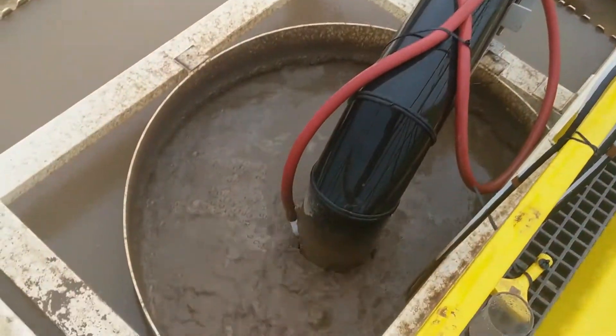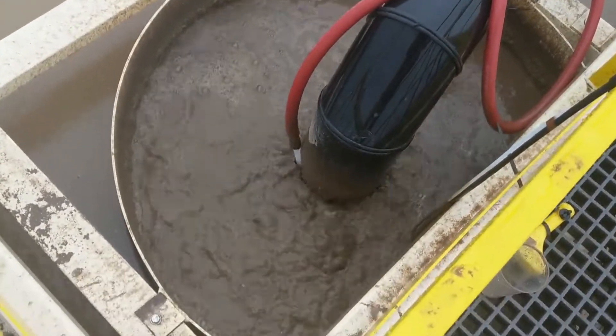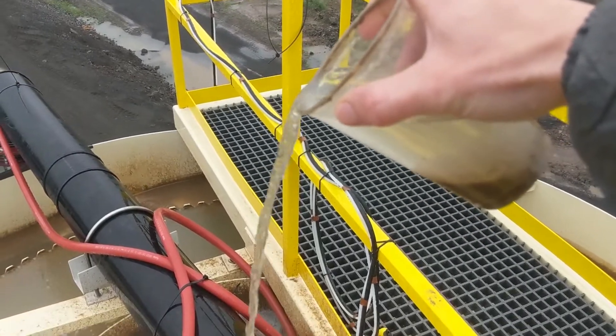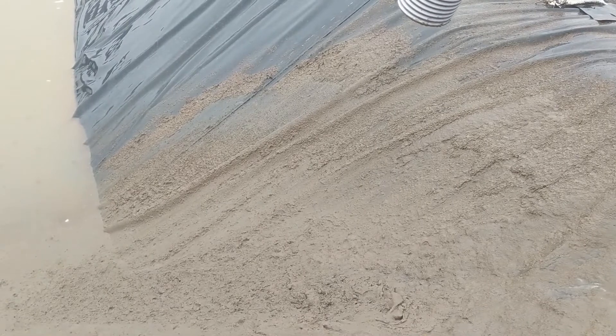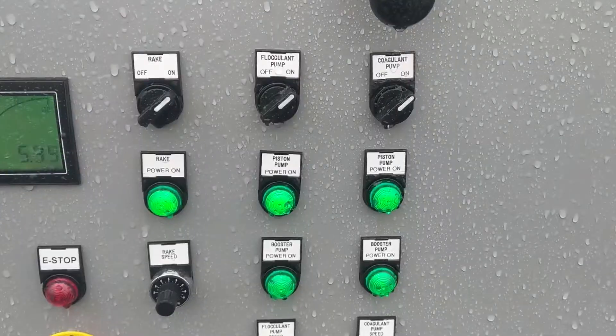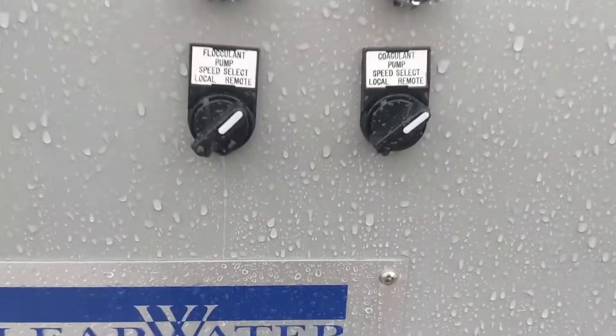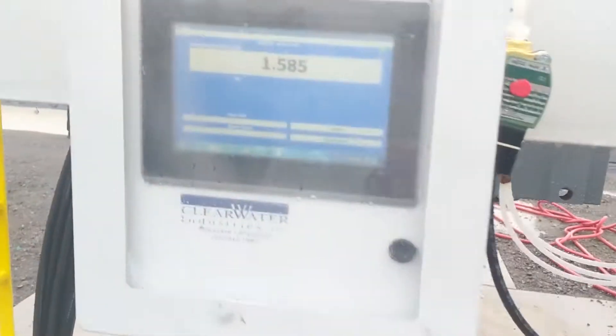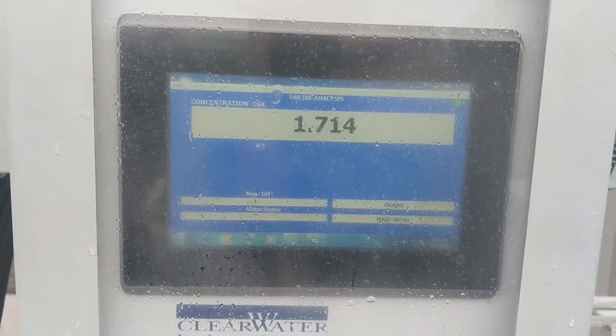You can see we're maintaining good floc formation, we've got clean water, and now we're discharging some really nice mud — that's really good, that's the star of the show here. Here are our control options; we've got everything in auto, running remote or automatic speed.